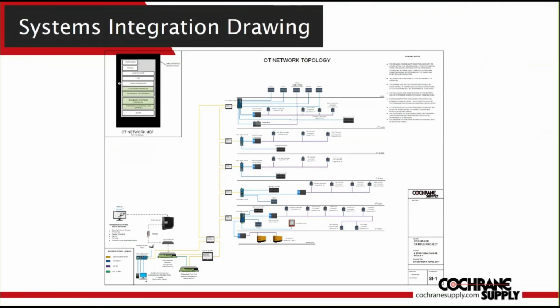I see that they want redundant front-end network managers. I see that they have an on-site server. I see that they want wireless access. And I see that they're using Niagara. And in the top left-hand corner, you're going to want it all in a server rack.